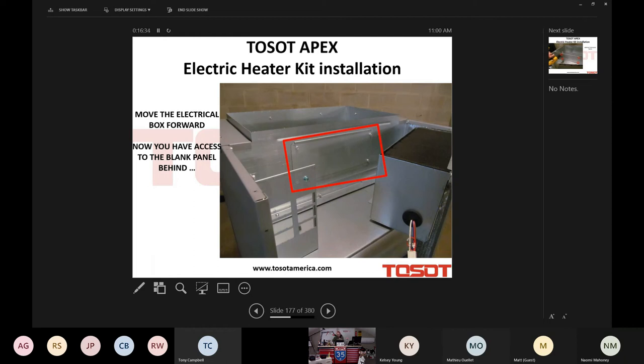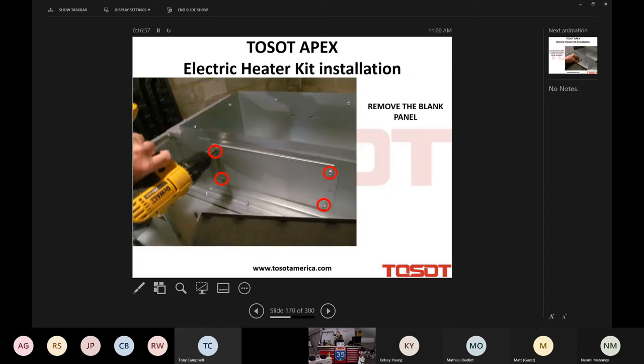Now, if you're retrofitting, if you're doing this after the fan coil has actually been installed, you're probably going to want to completely move that box out of the way just to give you a little bit more maneuverability. And that's fine. You can do that. To do that, you're simply going to disconnect it at the blower motor. Molex connector, no big whoop, right? But probably going to want to completely move it out of the way to give yourself a little bit more room there. We need to remove that plate.